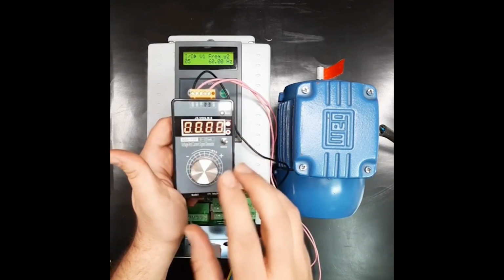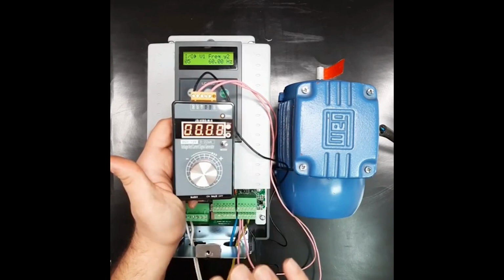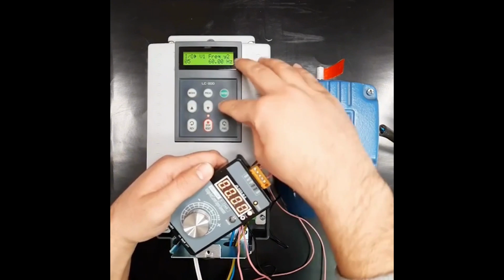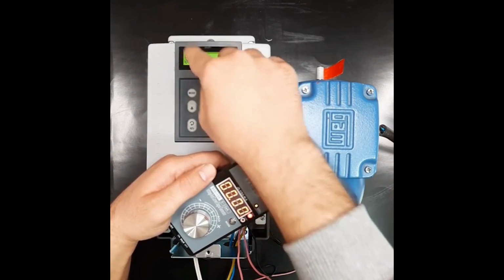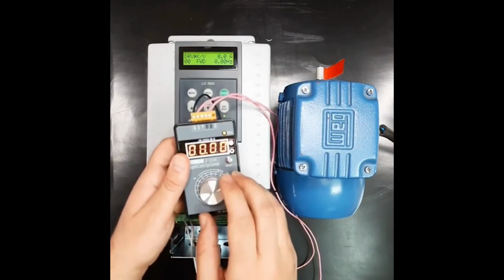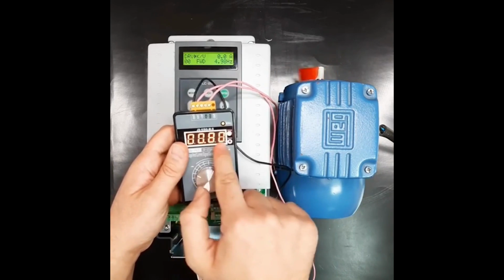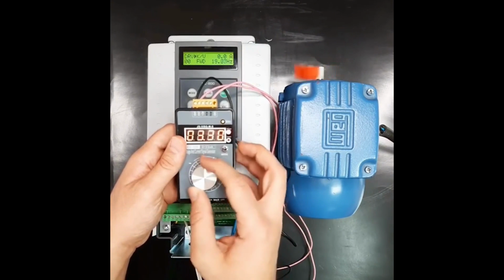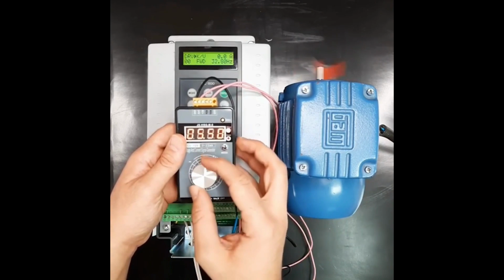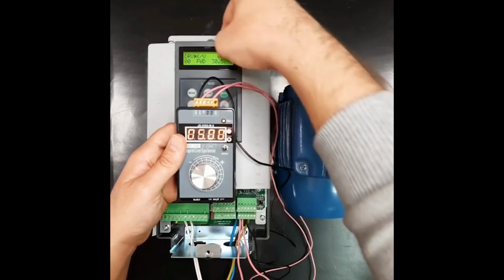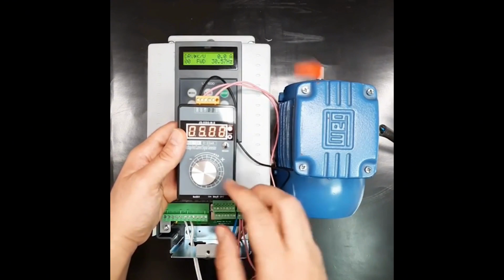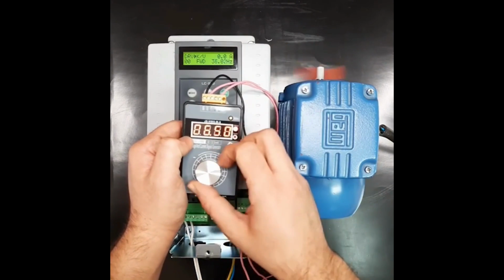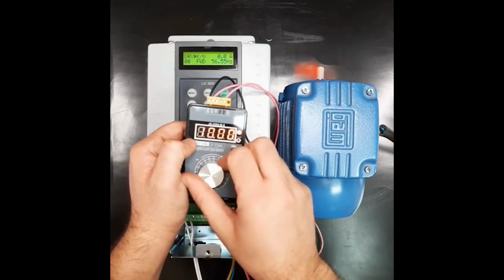I've connected the module to the drive. Now the 0 to 10 volts that the module applies to the drive controls the motor from 0 to 60 Hz. Since we're starting up using the keypad, I'll run the motor. And when I turn the knob, the frequency changes according to the voltage I provide. As I increase the voltage, you can see that the frequency starts to change. For example, if I set it to 5 volts, it shows about 30 Hertz. I'll go up to 10 volts, and when I give 10 volts to the drive, it increases the frequency up to 60 Hertz.